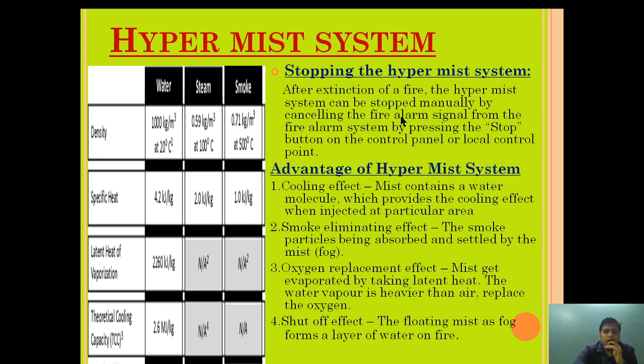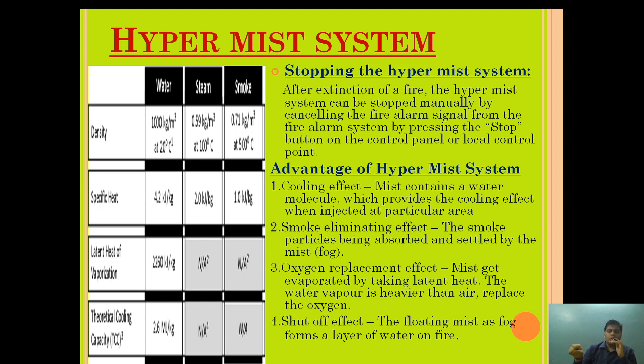After the extinction of the fire, the Hypermist system can be stopped manually by turning off the pump, or by cancelling the fire alarm signal from the fire alarm system, or by pressing the stop button on the control panel or local point. Once the fire is extinguished, we press the button on the local or main control panel and the pump stops and water injection stops.